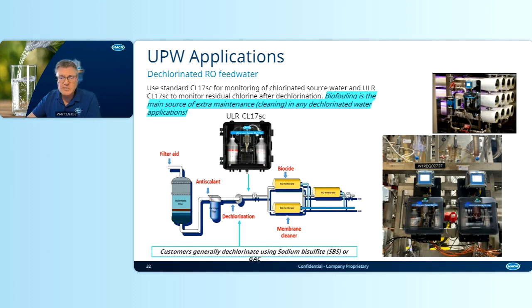The ultra pure water applications require some special note and special attention here, because the water is normally dechlorinated in those applications. And if it's dechlorinated, once again, the main instrument to use is the ULR version of the CL17. What is very common and important about dechlorinated water? It's biofouling. It's the main source of extra maintenance, which is cleaning of the instrument itself, the measurement cell, and the flow meter, if it's connected, because the flow meter can be bypassed. As I mentioned, it's an optional device.